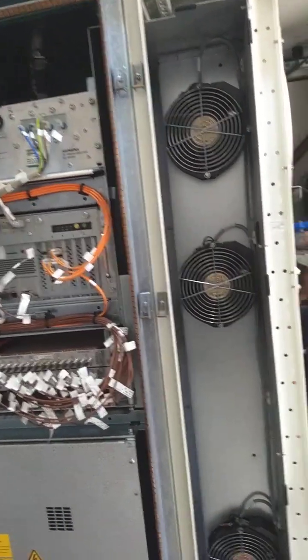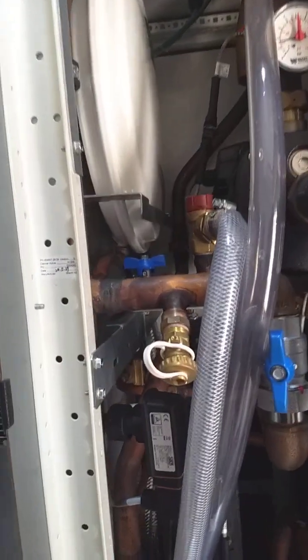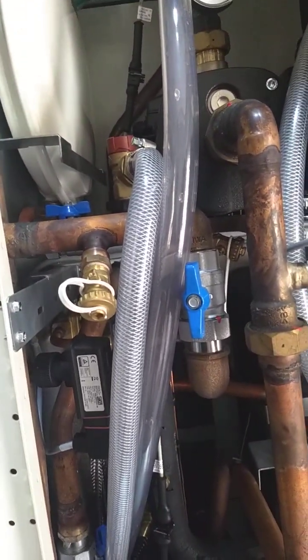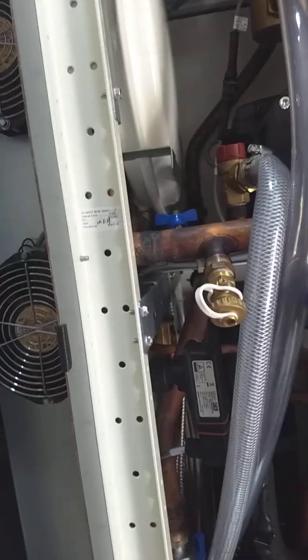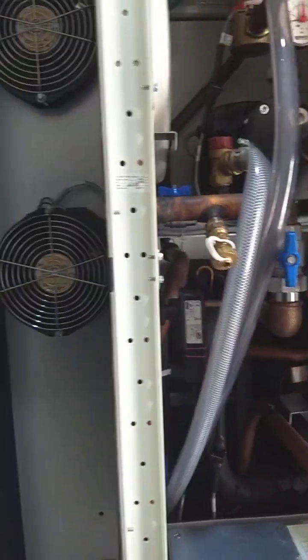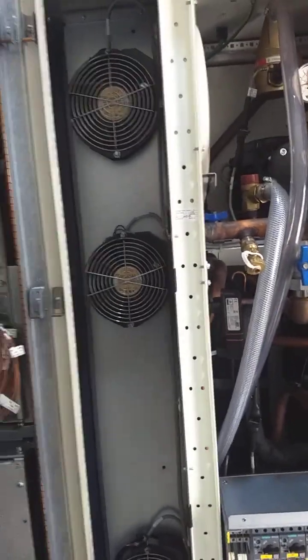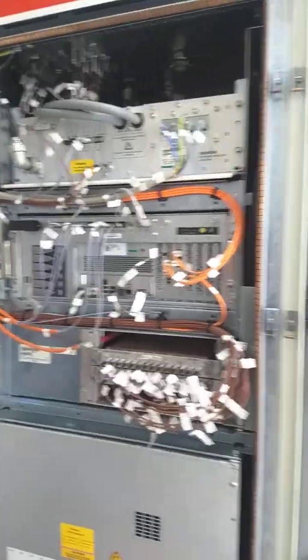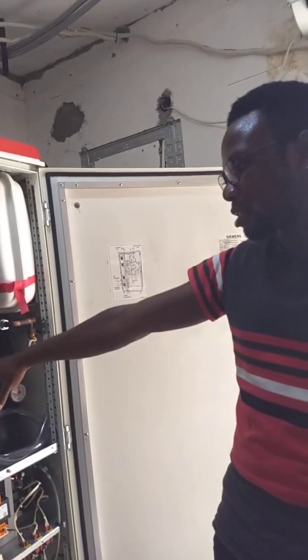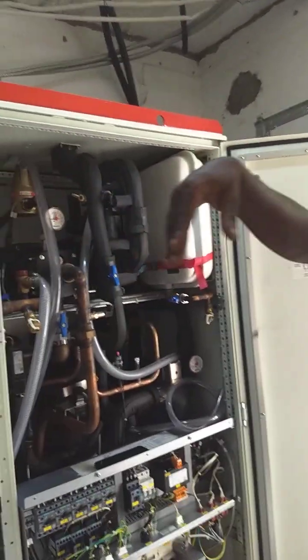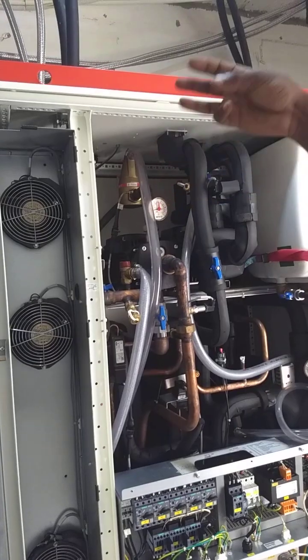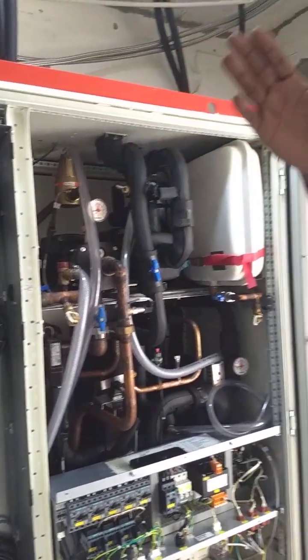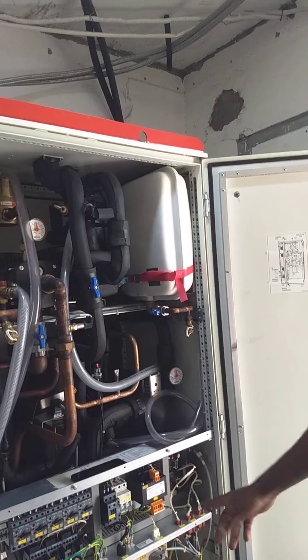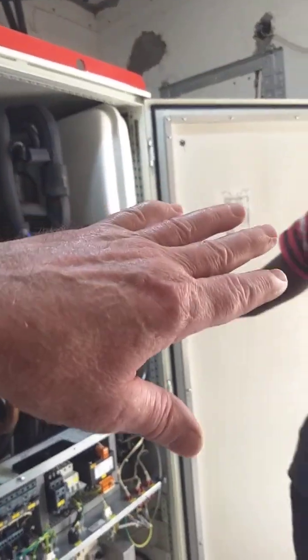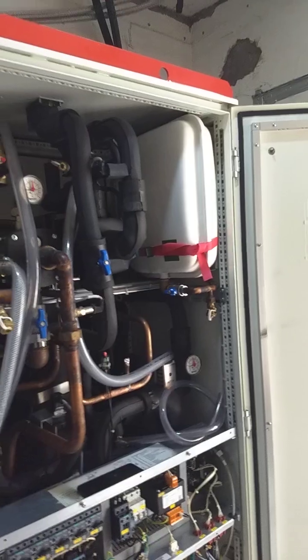So there are separate circuits. Are there like three separate circuits for the coolant, or just one? Is it common, or is it different? The secondary is a combination. From here, all the cold is going to all of these places which I have mentioned. The hot one will come to the heat exchanger, and then the cold one goes out to the gradient, radio frequency amplifier, and compressor. And the heat exchanger is connected to the large fan outside? Yeah, the heat exchanger is an interface between the primary circuit and the secondary circuit.